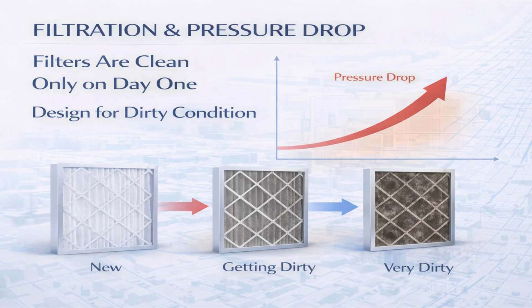What makes this issue particularly difficult to identify is how it develops. The system does not fail suddenly. There are no immediate alarms. Performance simply declines over time. The space slowly begins to feel unconditioned, cooling capacity appears to drop, and the problem is often blamed on equipment aging or poor maintenance. In reality, the root cause is usually much earlier: a selection decision that did not allow sufficient fan capability for filter loading. This is why designing for clean and dirty conditions is essential. It ensures stable airflow, consistent comfort, and reliable performance throughout the system's life, not just at commissioning.